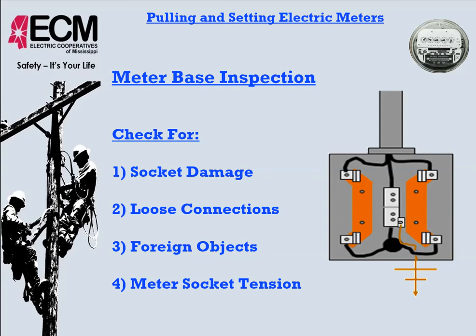But definitely when we come back here sometime later to remove that meter, if these plastic insulators are broken, the guts and all that will come out with the meter base. The hots here on the top and the hots on the bottom, the line and the load side lugs, will come into contact with the grounded meter base, which will cause an arc flash situation, possible electrocution as well. Loose connections, there again, is something to be aware of.